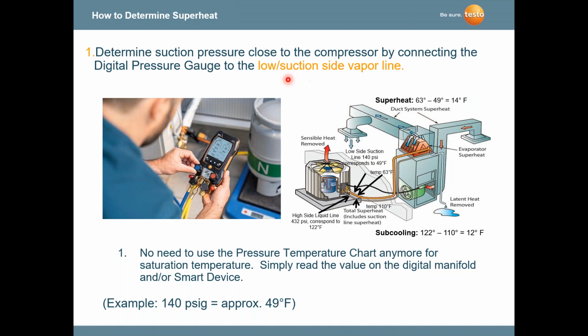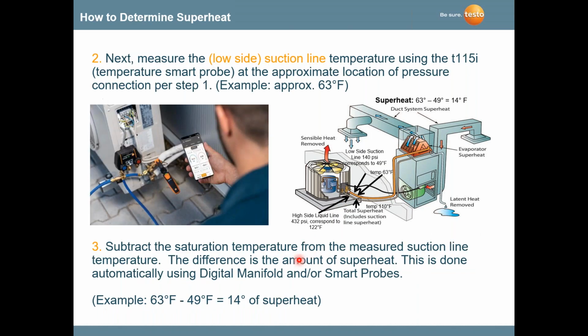So what you're looking at here is connecting the digital pressure gauge to the low suction side. You'd have the blue hose connected to the low side. You have a pressure temperature sensor, a wireless probe, connected to the low side suction line, and the instrument's going to automatically calculate for you the saturation temperature and the superheat. Very quick, very fast, very accurate. Again, here you're looking at the low side suction line temperature using a thermometer, a wireless probe, and getting the calculated superheat automatically.